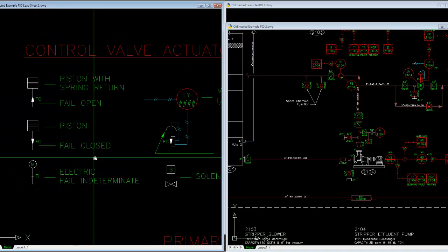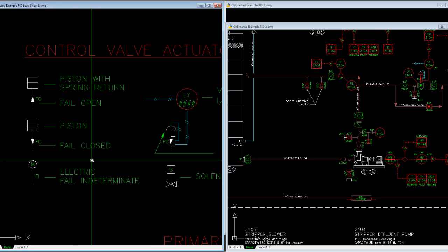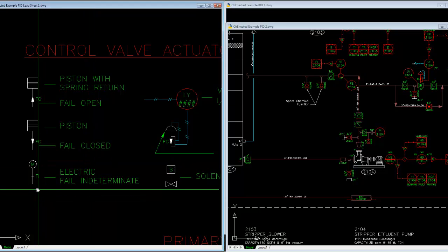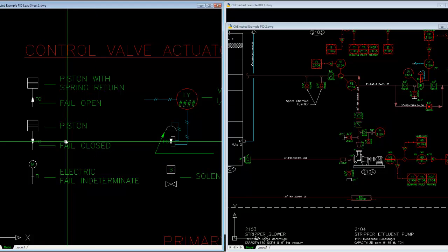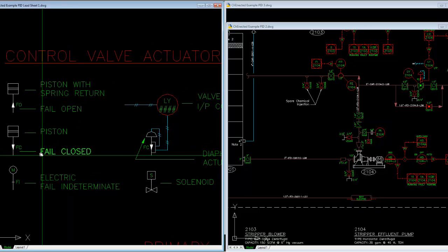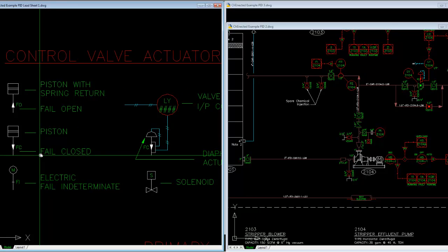Or the one last one is fail last position, which is sometimes shown, which is FLP. I'm not showing that here, but that would be a good case for a valve that wherever it failed, wherever it was when you lost control of it, it's probably still there.